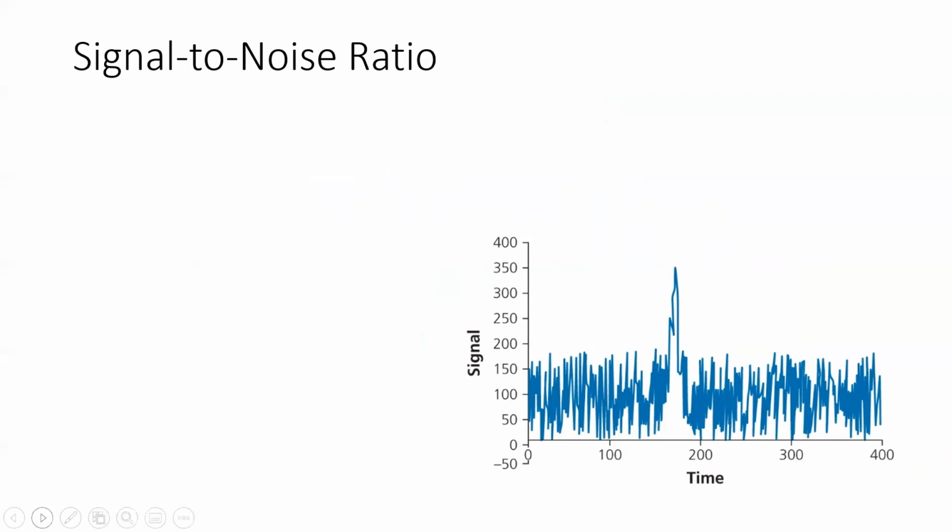And we talked a little bit at the beginning in chapter 1 about how a signal to noise ratio of 3 is our limit of detection. Who remembers what limit of quantitation was? That's right, 10. Yeah, and so we need a signal to noise of 3 to say, yes, that is a signal, and a signal to noise of 10 to say, I can tell you how much signal that is. That's essentially what these two mean.